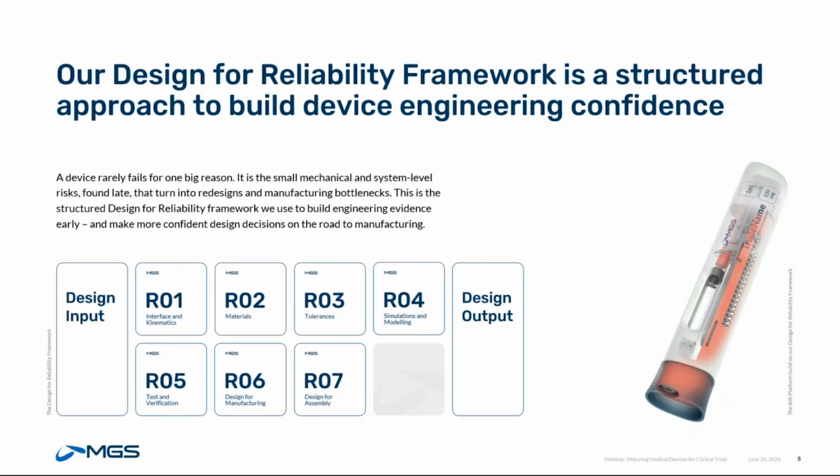So, for instance, with the AIR auto-injector platform, you would most likely use some of the disciplines to investigate how the power spring and its interfacing components work and how you can reduce the risk related to that. You don't have to focus as much on the housing, for instance, that doesn't carry the same amount of load.